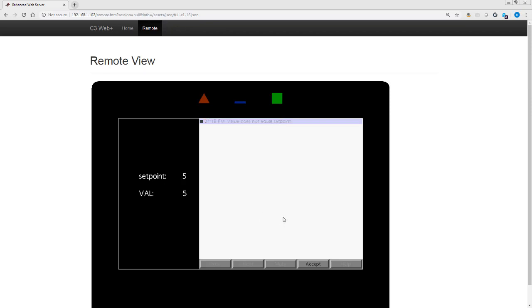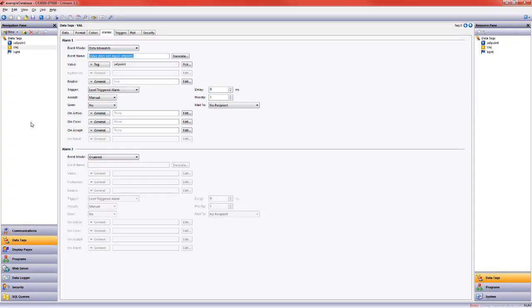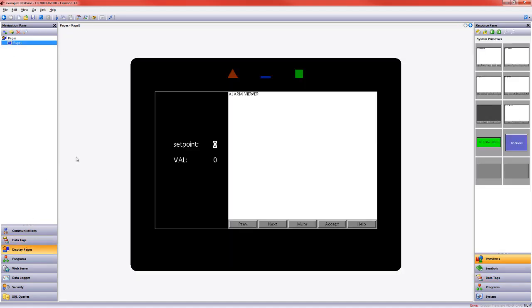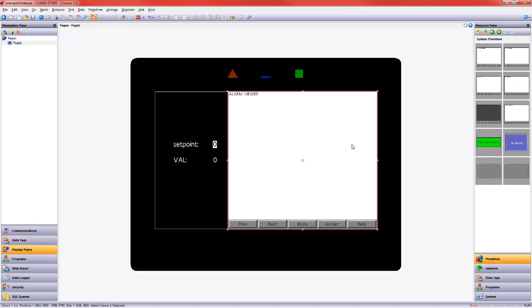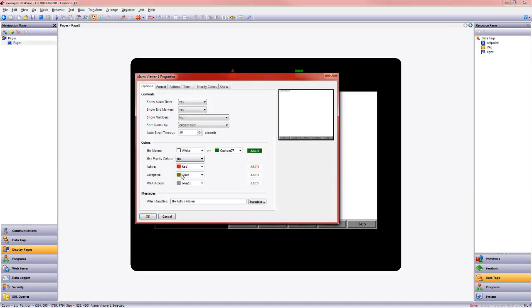Now let's say I accept it while it's true. That was a third color option you'll remember. If I go to display pages, properties for the alarm viewer, that's that accepted olive. So we can see that when it's active, it's red. When it was active, is no longer, and we're waiting for the operator to accept it, it's gray. And in this case, if it's still in active condition, it will turn that olive color.